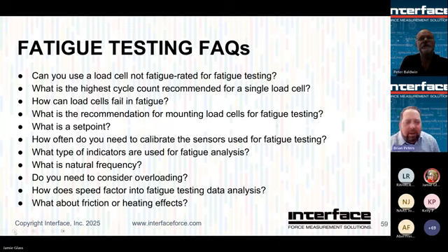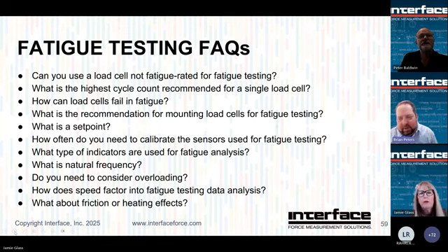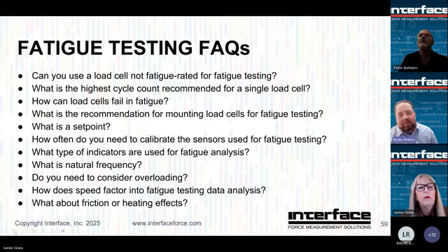Good. All right, last one. What about friction or heating effect? So this is an interesting question. I think from a sensor standpoint, there is no internal friction or heating that's occurring, regardless of cycle speed. So for the load cell, it's not an issue.